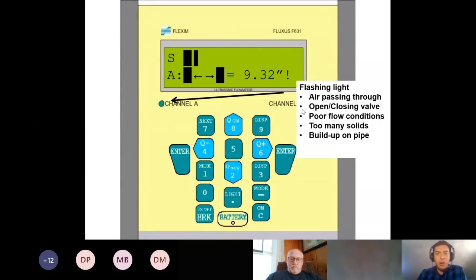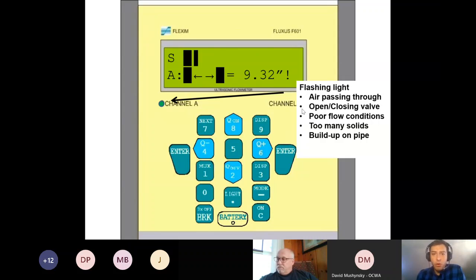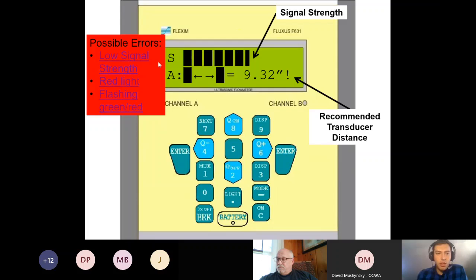It could be too many solids in the pipes. It can read up to 5% solids, but too many solids will affect that signal. And then this could also just be very bad buildup on your pipe. Again, try to find somewhere else in the line, or if you really can't do that and you want to put a flow meter there, cutting into the pipe and putting in a clean spool piece, a stainless steel spool piece, you'd get a very good signal and that would stop. Those are the possible errors when it comes to the signal strength and the channels being red or green.